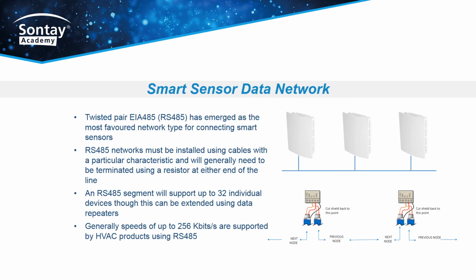Here is the Smart Sensor Data Network. It consists of twisted pair EIA485 or RS485, which has emerged as the most favoured network type for connecting smart sensors. RS485 networks must be installed using cables with a particular characteristic and will generally need to be terminated using a resistor at either end of the line. An RS485 segment will support up to 32 individual devices, though this can be extended using data repeaters. Generally, speeds of up to 256 kilobits per second are supported by HVAC products using RS485.